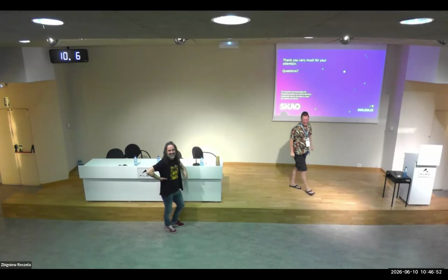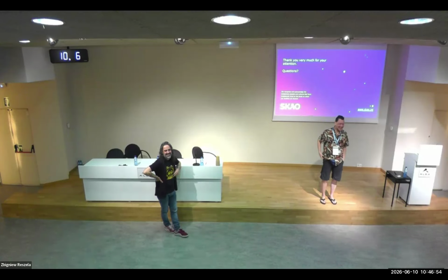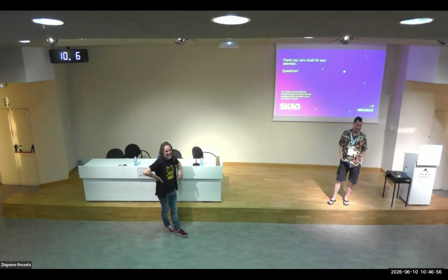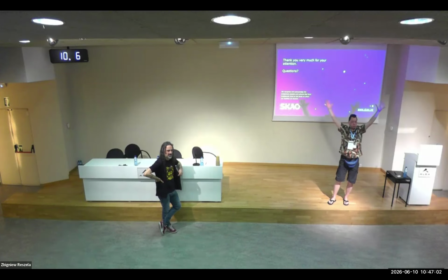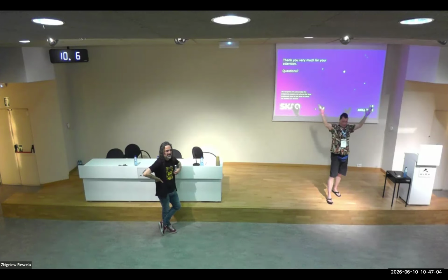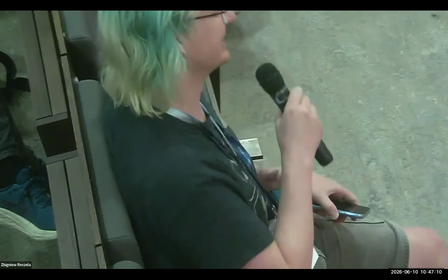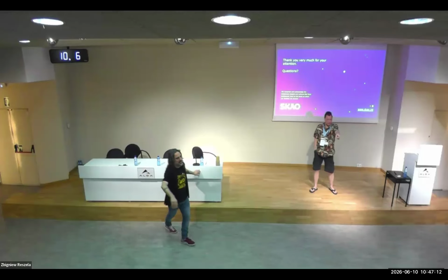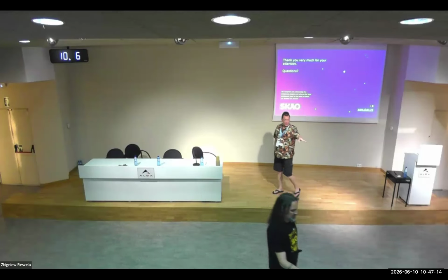Anders. We had some network issues or systems not working properly, where you then had all the 50 stations going off, sending alarms. And I can tell you the operators were not happy if you have more than 5 alarms. They immediately say, can we just turn them off? Yeah, exactly. And to tell you the truth, that's exactly my experience from LOFAR times.